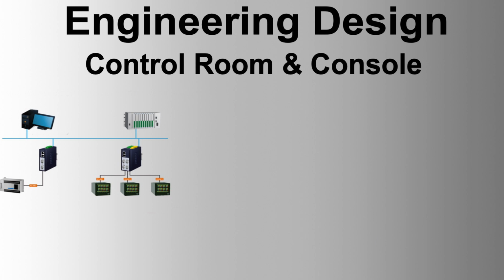Light and outside view. The lighting plan, based on the control room layout, locations of consoles, workstations, etc., should be produced at the earliest possible stage of the design. The illuminance at the work surface should be between 200 lx and 500 lx. The illuminance shall be adjustable by means of a dimmer and should be controlled from the console. If color VDUs are used, the maximum horizontal illuminance shall be 320 lx. The luminance ratios between the viewed object, the immediate environment, and the periphery shall be in the ratio of approximately 10:3:1.